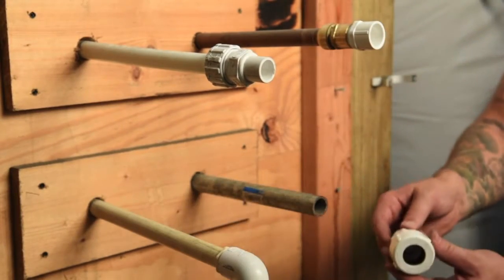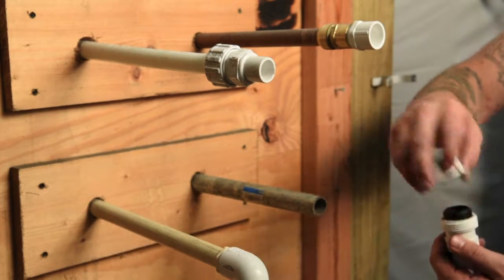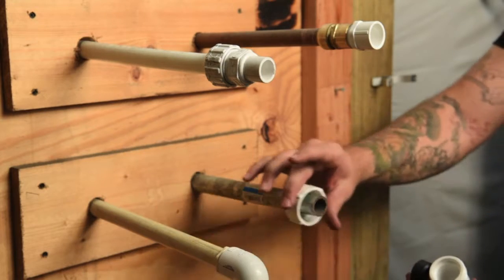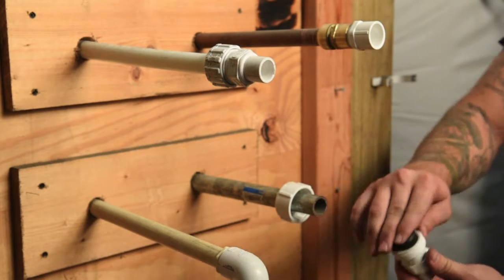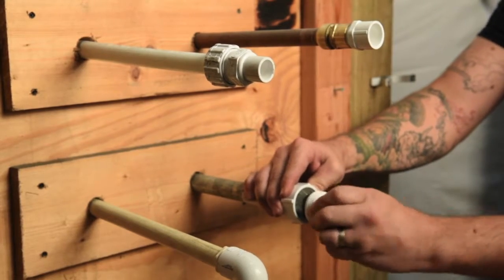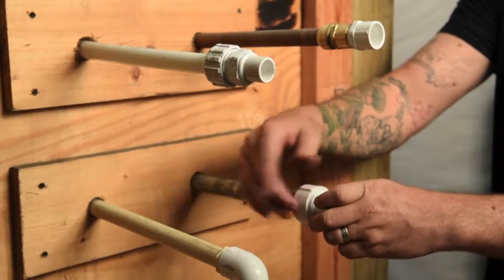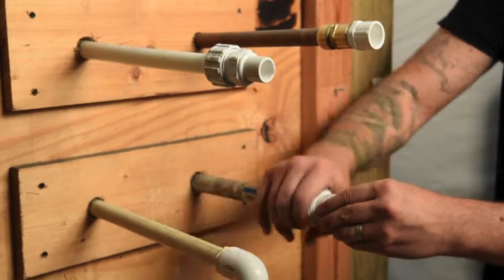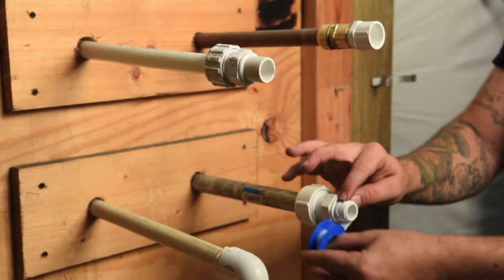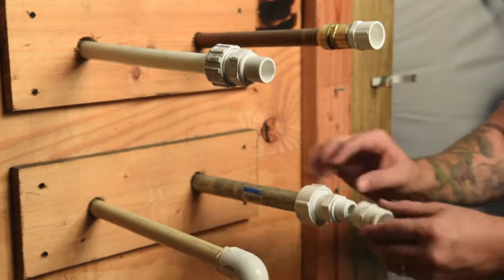Your second option for galvanized is another compression fitting. However this fitting has a compression side for the galvanized, with the other side being a male threaded end. After compressing onto the galvanized, the other side is wrapped in teflon and then either a female threaded 90 or female threaded coupling is placed on to the compression fitting.